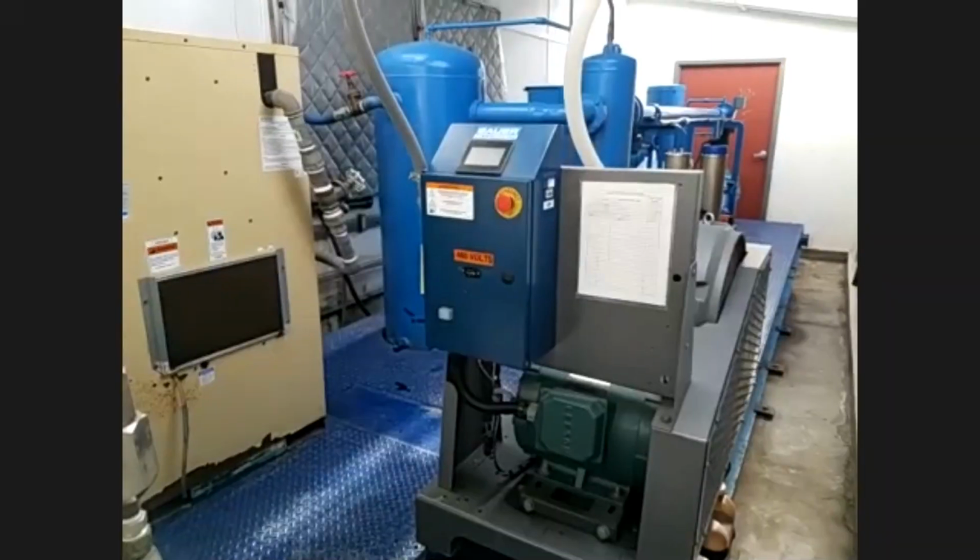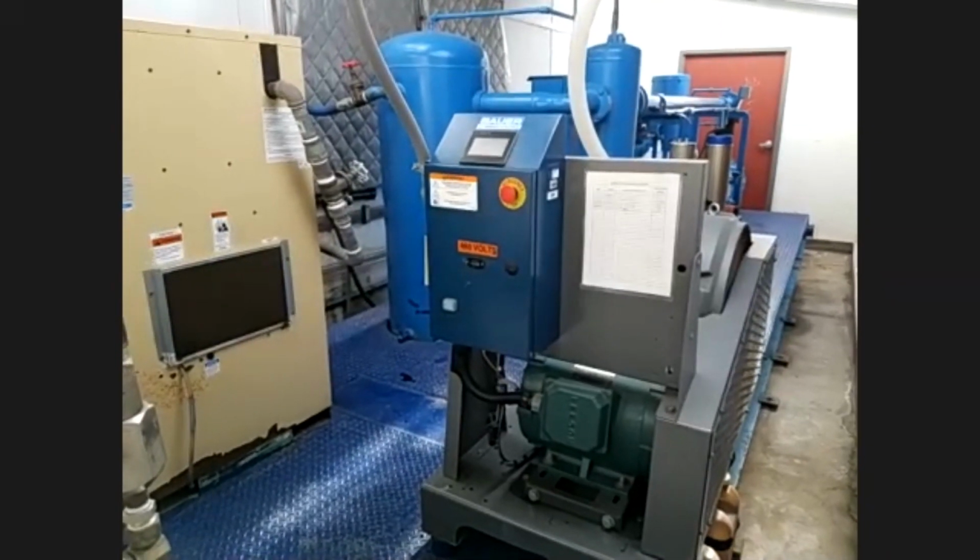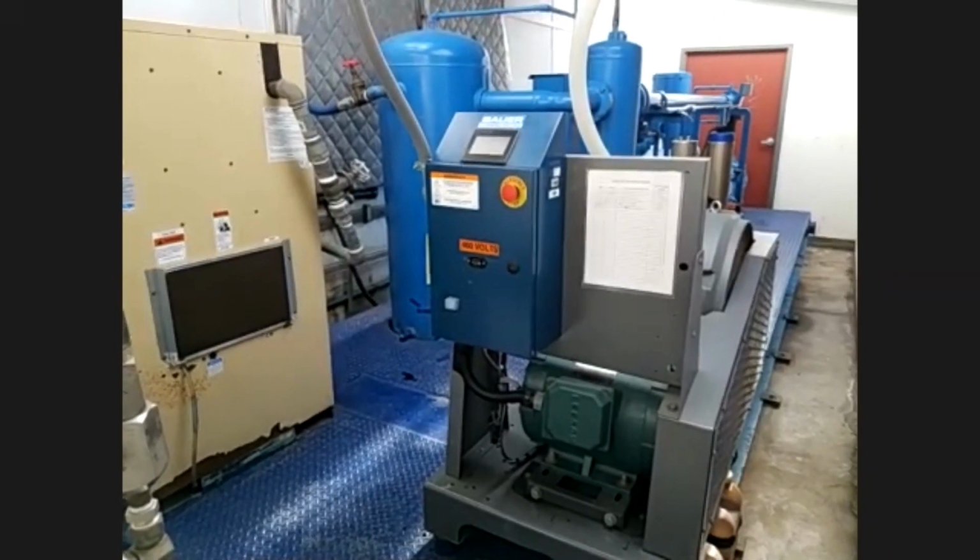Obviously, the way to get that air in, you've got a couple of compressors there. So I would assume having multiple compressors is sort of a key thing to make sure the chamber can be operational. Because obviously, if they all go down, we got a problem. And as I recall, wasn't that an issue a couple of years ago that we needed to replace one of those compressors? We needed to replace the high pressure compressor a few years back, and then this past year we had to do a full overhaul on our low pressure compressor.